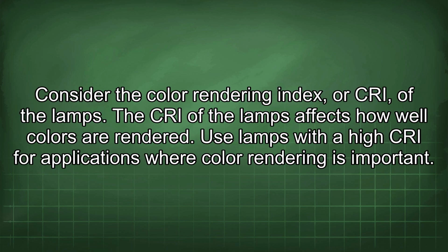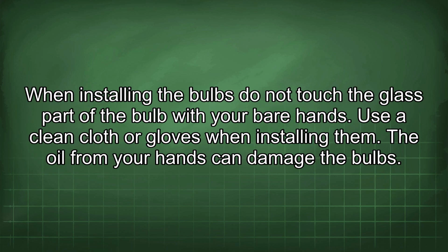Consider the color rendering index, or CRI, of the lamps. The CRI of the lamps affects how well colors are rendered. Use lamps with a high CRI for applications where color rendering is important. When installing the bulbs, do not touch the glass part of the bulb with your bare hands. Use a clean cloth or gloves when installing them. The oil from your hands can damage the bulbs.